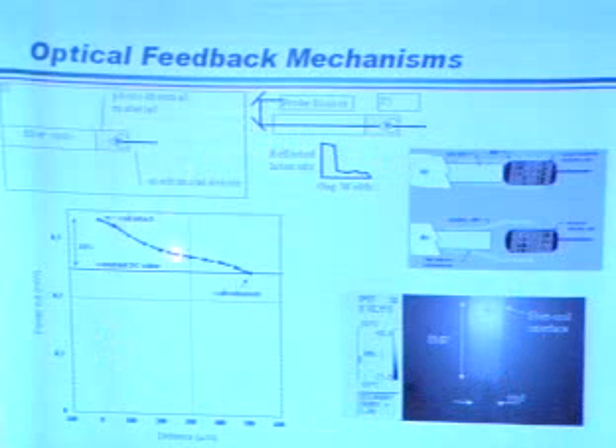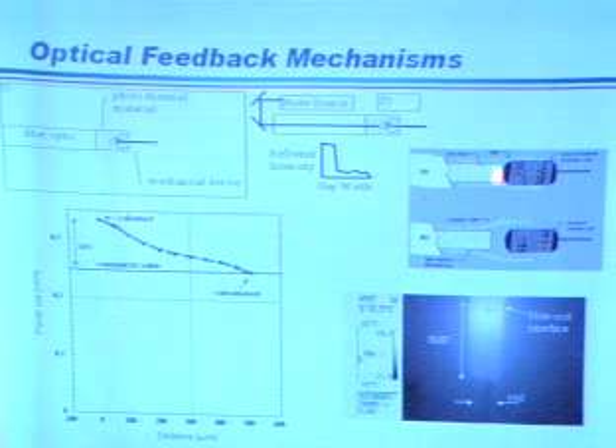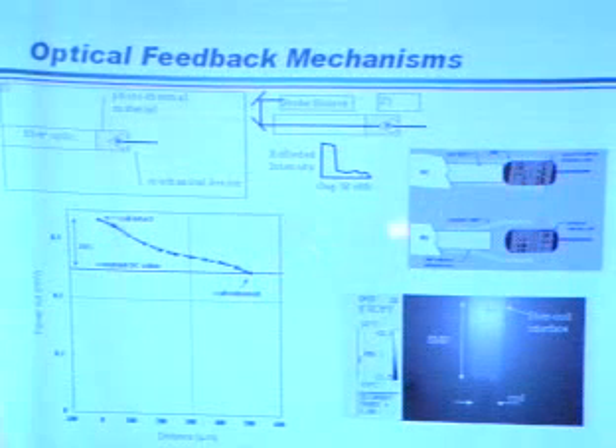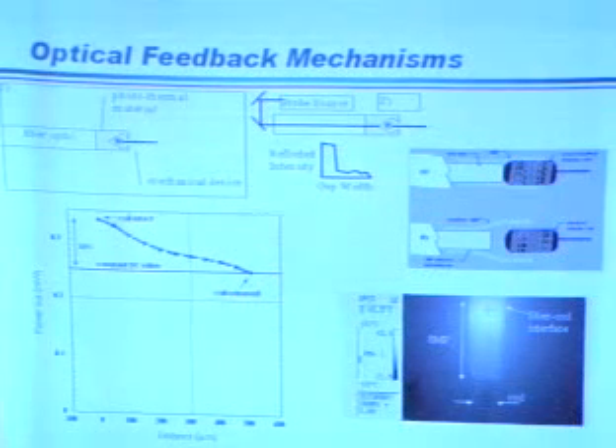And then there's a further advantage of using fiber optics. You can look at the reflection intensity changes. When it's intact, for instance, the coil is butt against the fiber optic, and you have a high reflection efficiency. But at the opening, the coil release, which is kind of critical for a feedback mechanism, the gap is increasing and you know that it's released. Because the worst thing is that it's not completely released, you pull it back halfway, and then it releases, as I mentioned earlier.